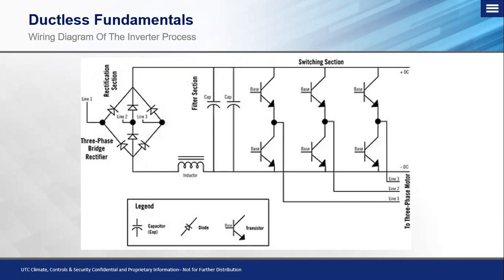So remember, we're simulating an AC sine wave. That compressor is AC. We're trying to fool it with DC voltage so that we can control its speed to a much finer degree. So we're pulsating voltage on a positive and on a negative bus directly to W, V, and U to simulate an AC sine wave and have a much finer control of that power, so that in turn we can control different percentages of speed, 20%, 40%, 60%, and so on. So these compressors are AC compressors.